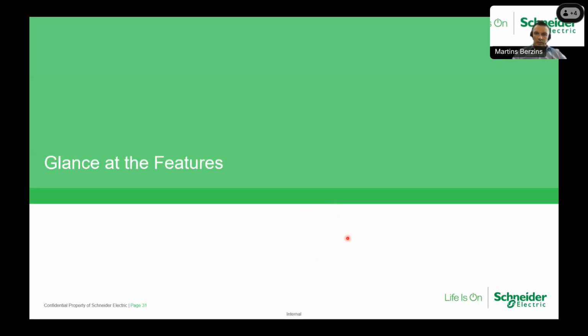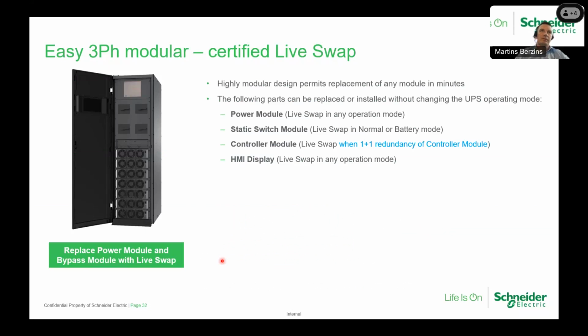So looking at the features, the 3-phase modular has this live swap certification. So what does that mean? This highly modular design permits replacement of a power module in a minute and without changing the operation mode. Also, the static bypass switch can be changed without interrupting the UPS from normal or battery mode. The controller, once we have a redundant controller, can be changed in any operation mode, and the display is also replaceable while the UPS is operating, so no need to put the UPS in bypass to do such actions.